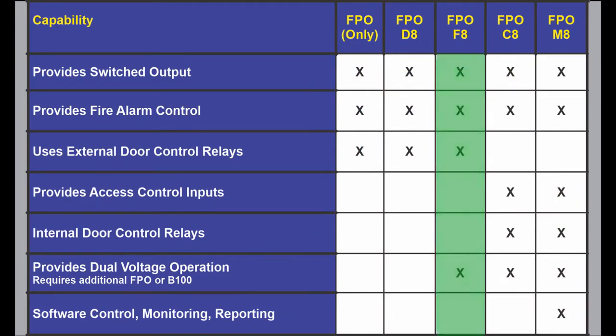You can use the FPO B100 F8 combination in a situation where you are using the access control system relays to control the doors and you have 16 doors. Again, 14 of them are strikes, two of them are mag locks, but in this case some are 12 volts, some are 24 volts, some strikes are fail safe, some are fail secure. You can use an FPO with two F8s.